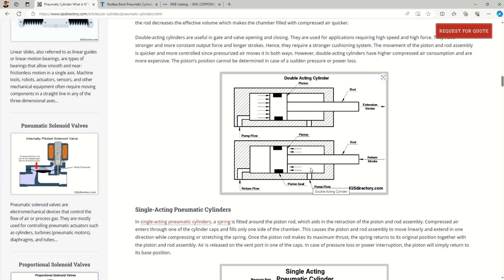For the return stroke, we switch the directional valves and pass air from the piston rod side, while air exhausts from the piston side — giving us the return stroke. Because we use air in both directions, it is called a double acting cylinder. The forces on both strokes will be different since the effective areas on each side are different.